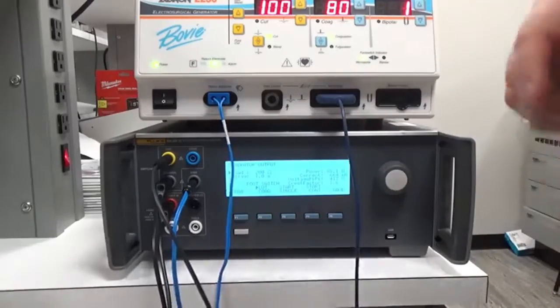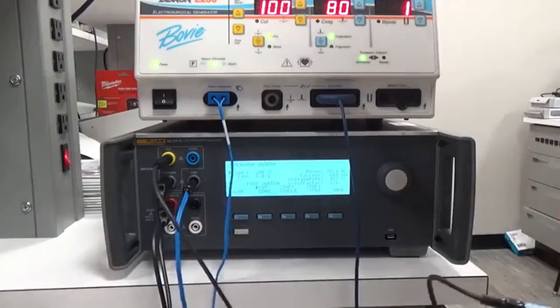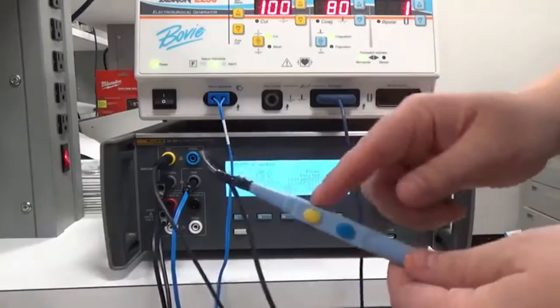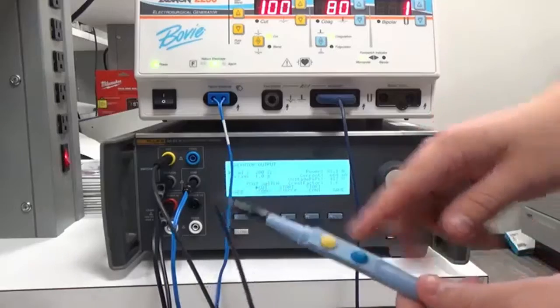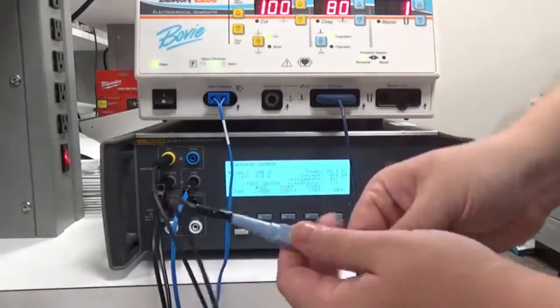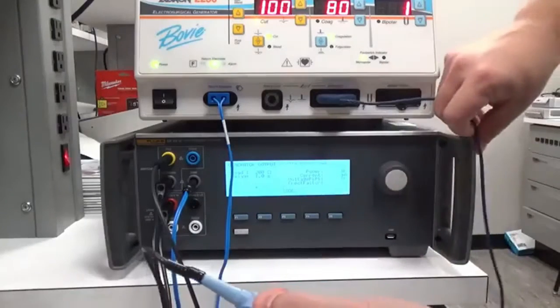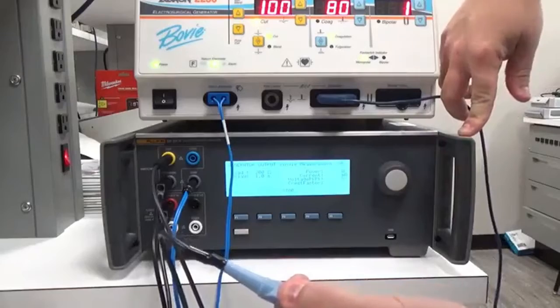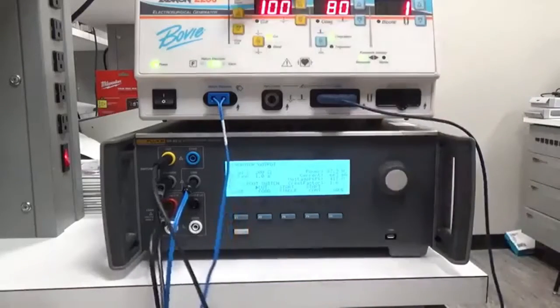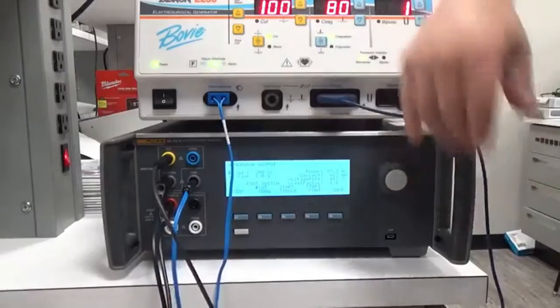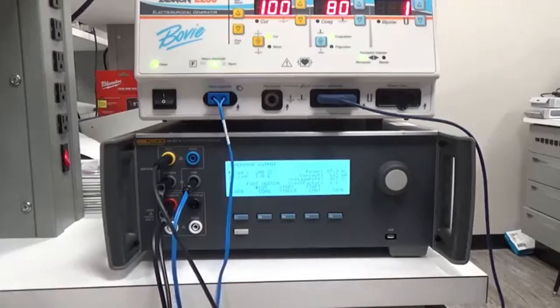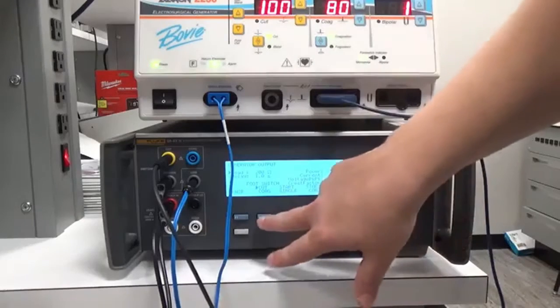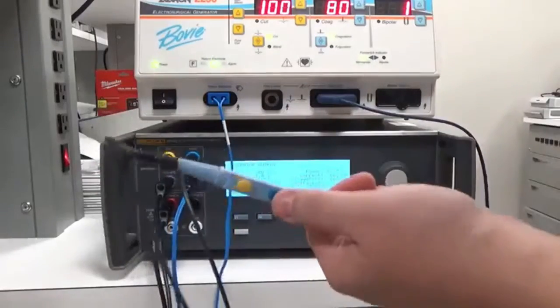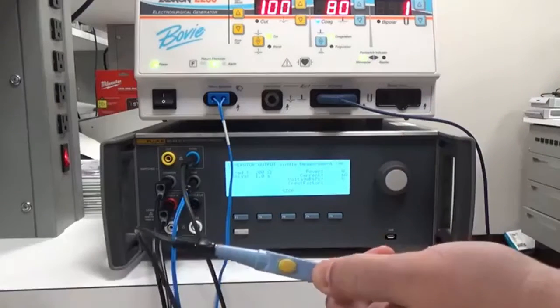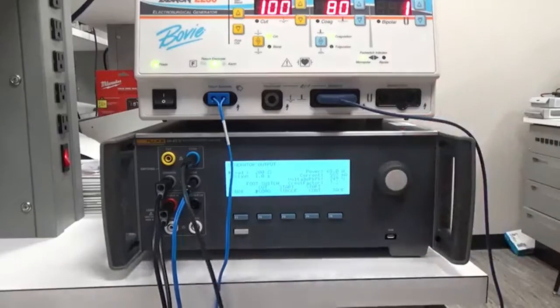The difference between this test and the test with the foot switch is that when I start the test, I actually need to hit the appropriate button depending on what type of test we're doing. Because we're doing cut, I'll be hitting the yellow cut button. And as you can see, the numbers came up just as you would with the foot switch. No difference. 87.9 watts, 663 milliamps, etc. If I wanted to do coag, I would just change the coag here. I would change my port to the coag port, and I'd be hitting the coag button. And there's our information displayed there.